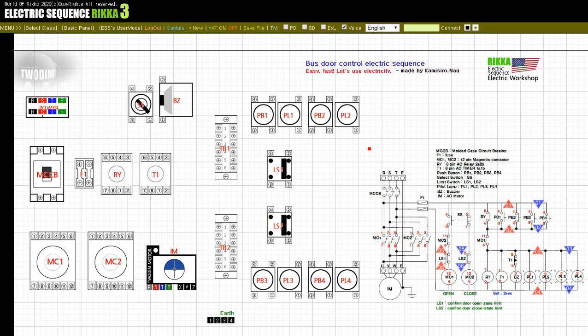When the vehicle arrives at the destination and the bus driver turns the selector switch SS to open the bus door and inputs it, power is supplied to the magnetic contactor MC1 and the motor rotates in the forward direction. The limit switch LS2 input falls as the bus door moves, and the bus door moves further to reach the limit switch LS1. At this time, LS1 is input and the motor IM is stopped.